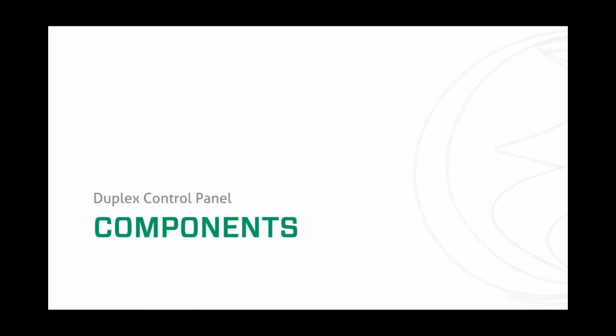So let's move on to duplex control panels. Again, for anybody that's new out there, who doesn't understand what the term duplex is referring to, we're referring to two pumps. It's a two-pump system. Pumps in these systems are typically alternating, so each takes a turn running. Generally in these panels, both pumps could be called to run at the same time if needed. Because of this, these panels will typically require an additional electrical circuit, which can be very important to make sure you get that addressed ahead of time.